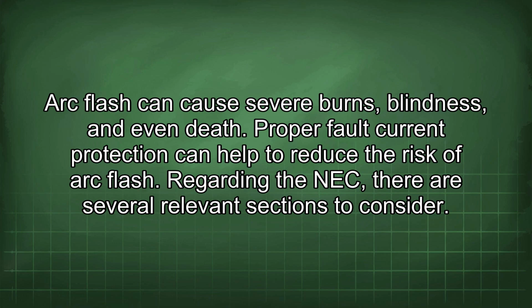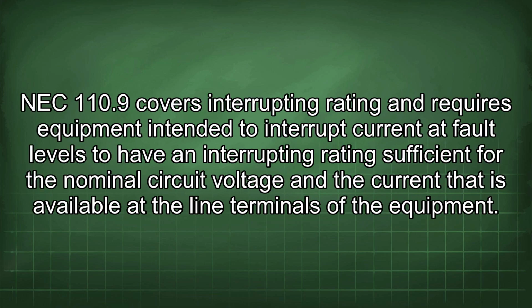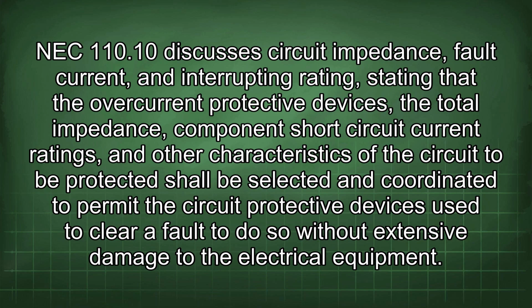Regarding the NEC, there are several relevant sections to consider. NEC 110.9 covers interrupting rating and requires equipment intended to interrupt current at fault levels to have an interrupting rating sufficient for the nominal circuit voltage and a current that is available at the line terminals of the equipment. NEC 110.10 discusses circuit impedance, fault current, and interrupting rating, stating that the overcurrent protective devices, the total impedance, component short circuit current ratings, and other characteristics of the circuit to be protected shall be selected and coordinated to permit the circuit protective devices used to clear a fault to do so without extensive damage to the electrical equipment.